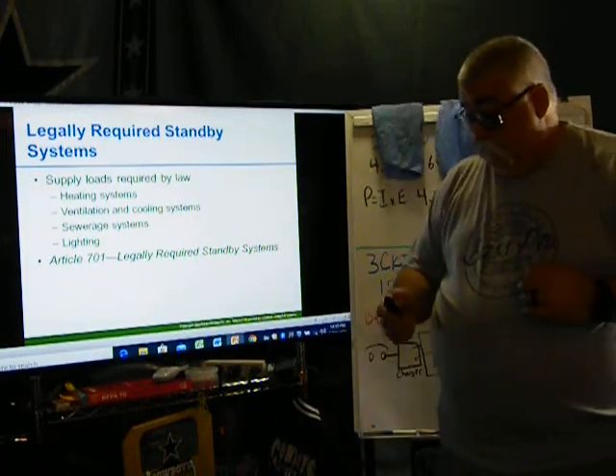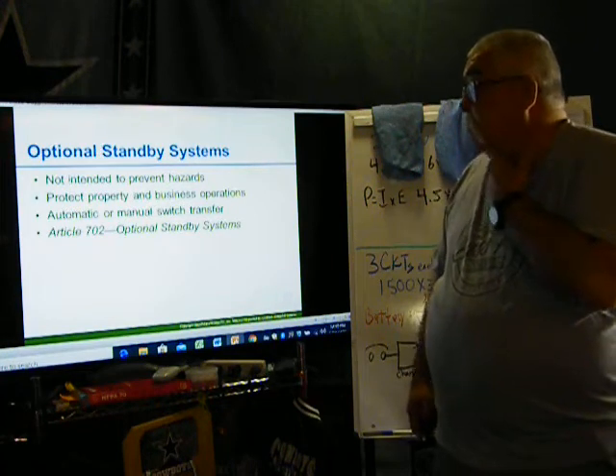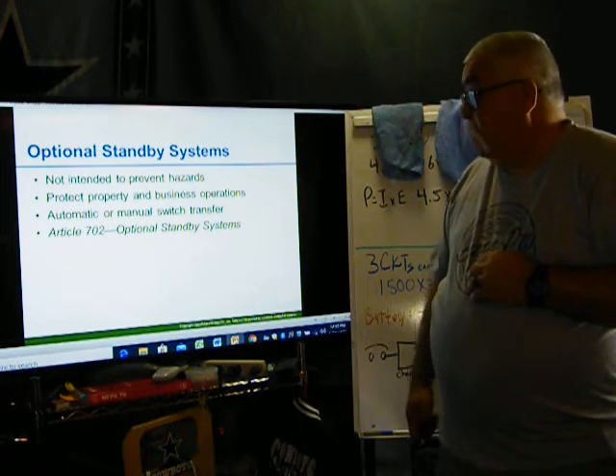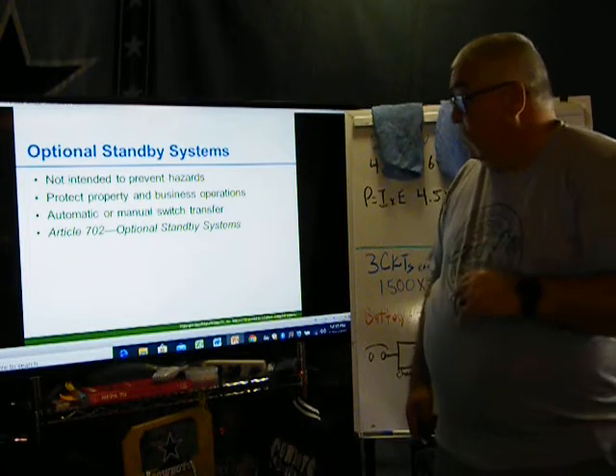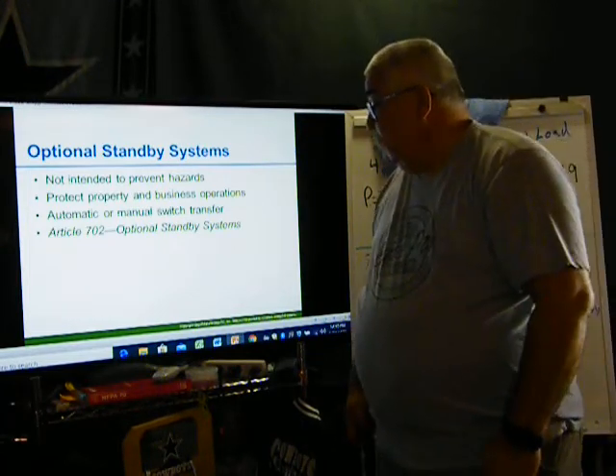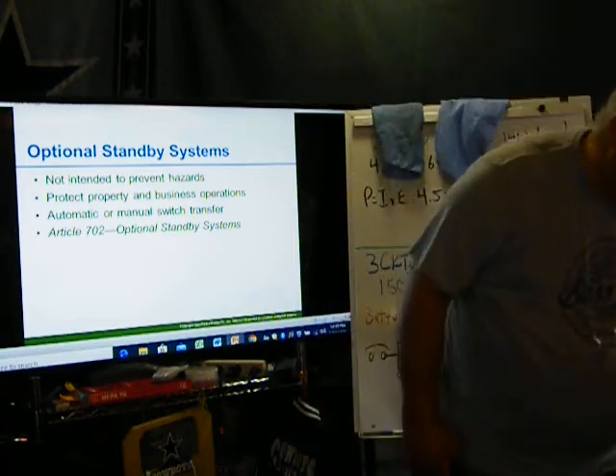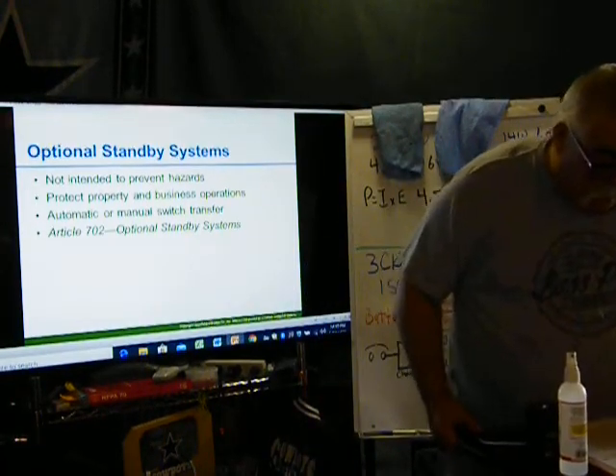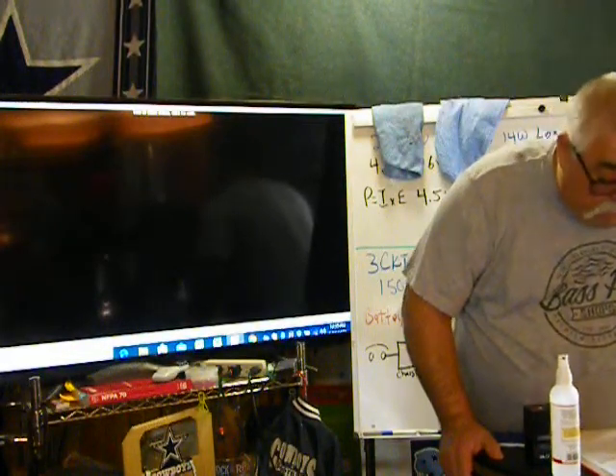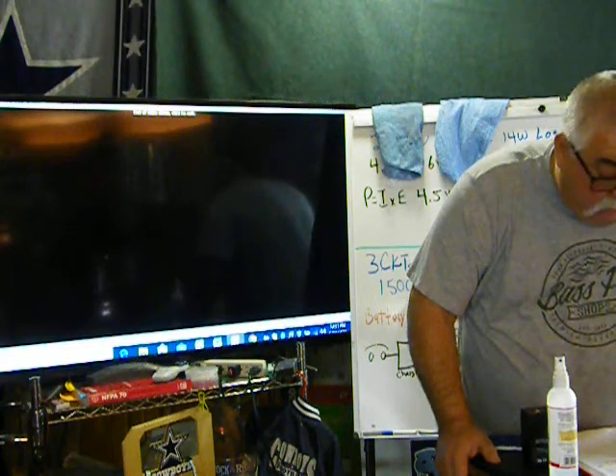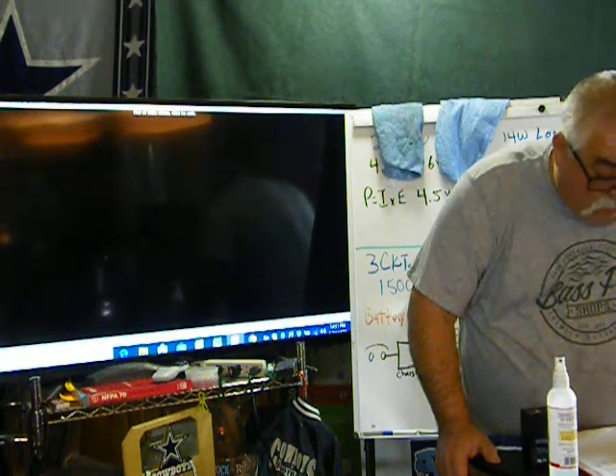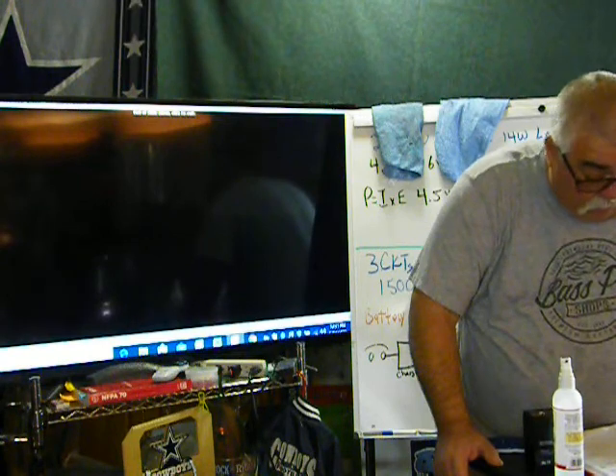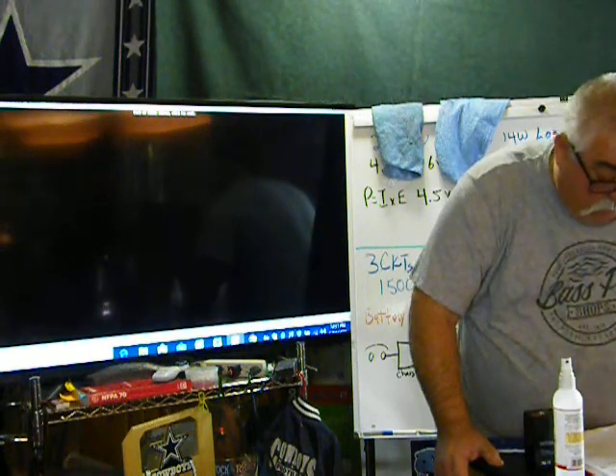Okay? Optional standby systems are not intended to prevent hazards, but to protect property and business operations. It can be automatic or manual. And these are all in Article 702, optional standby power. Okay, optional standby systems are not intended to prevent dangerous or hazardous situations. They are intended to protect property and business operations. These systems provide power to selected loads by either manual or automatic transfer. Typically, the following loads may be included. So you have a refrigerator, the heating unit, computer, data processing, communications, manufacturing, alarm systems.